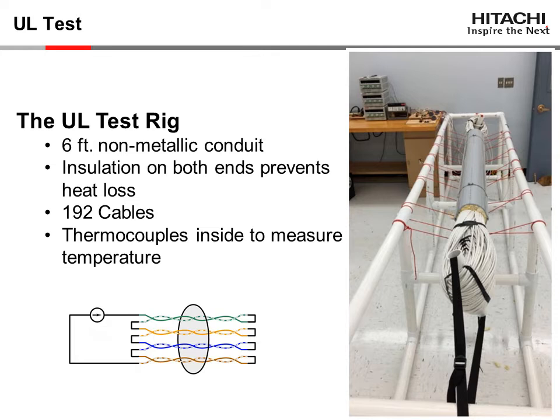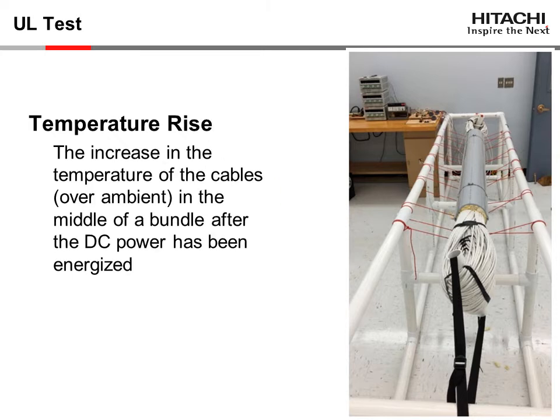A current is then applied to each pair, inducing a temperature rise. The temperature rise, above ambient temperature, in the middle of the bundle, is recorded as the amperage is increased. This continues until the overall temperature exceeds the maximum operating temperature of the cable.